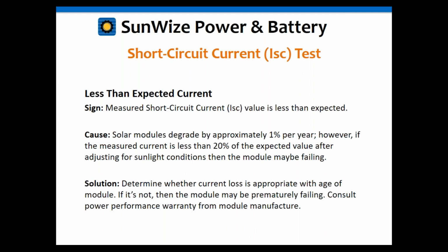Again, I mentioned degradation. Solar modules can degrade by as much as 1% per year. So if you've got a module that's been out there 20 years, it can degrade by 20%. So an 80% output might be enough still. I mean, the module hasn't necessarily gone bad. You're still getting 80% out. But depending upon how tightly your system was designed, that degradation may be a problem with supporting the load still.